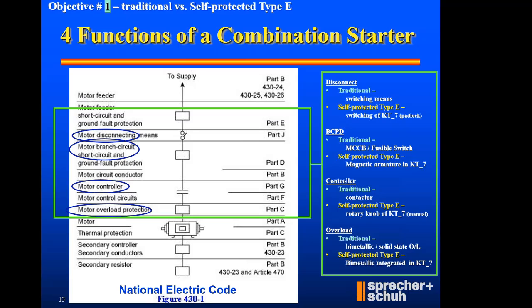Moving down in the National Electrical Code, we have to have some sort of a controller for a magnetic starter. So from a controller perspective, comparing traditional versus self-protected: in a traditional circuit, that's where your contactor comes in. That's what I said in a traditional, disconnect plus contactor plus overload. The contactor is your controller. From a self-protected Type E compliance to the controller, that's what the KTA7 does. It is a manual controller, meaning you have to walk up to it and use that rotary knob, but you get the means of opening and closing contacts of a controller. So that is a manual control.